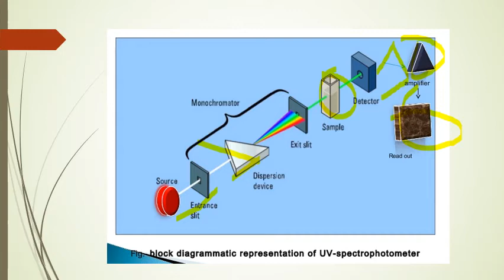One of the important features of the spectrophotometer is the source. In the UV visible spectrophotometer, the hydrogen discharge lamp is very much used for UV radiation, and for the visible we use a tungsten filament. Here you can see the hydrogen discharge lamp. The pair of electrodes is enclosed in a glass tube provided with a silica or quartz window for the UV radiation to pass through, filled with hydrogen gas. It is stable in nature, and it gives UV radiation of 120 to 350 nanometer. So it's a stable source for the UV radiation, and that's why it is specific for the instrument.